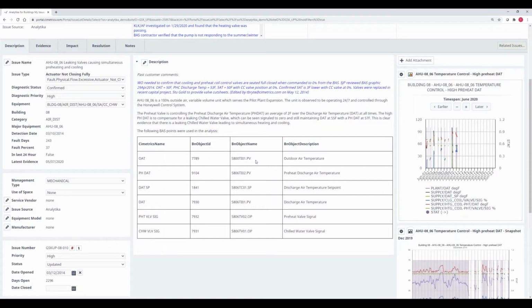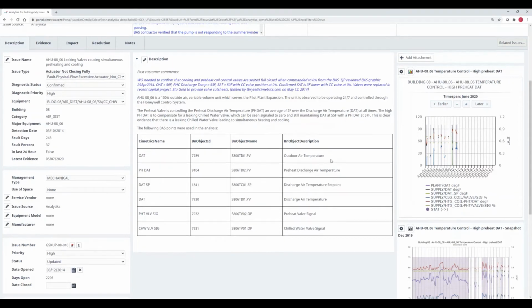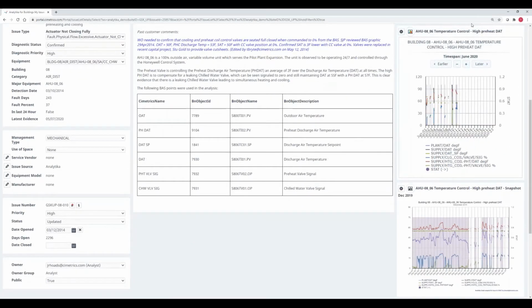Here's a list of the actual points from the BAS on site. This is the point name for the outdoor air temperature that we're using for this issue, and that is the actual point name from the site. So the building operator can go check their system using this point name, which cross-references to our point name here. Over here on the right-hand side, we can attach anything.